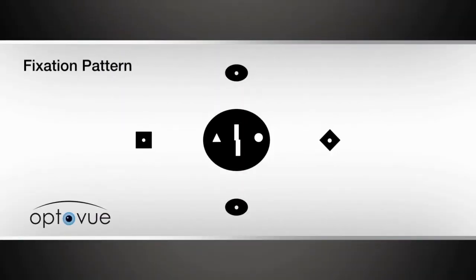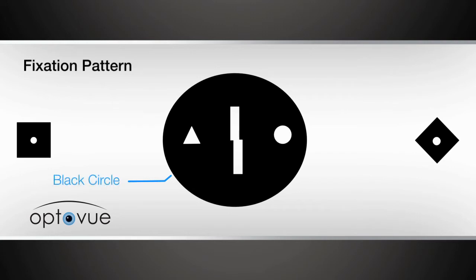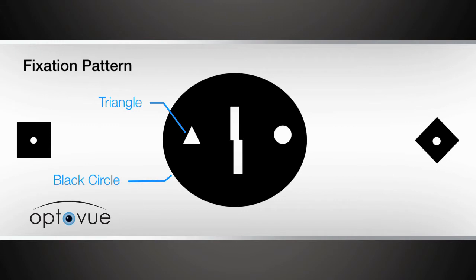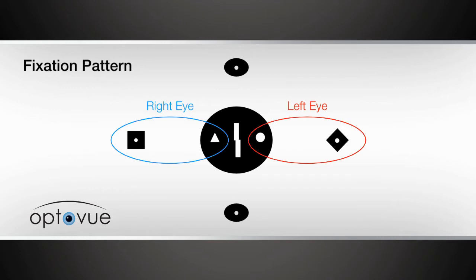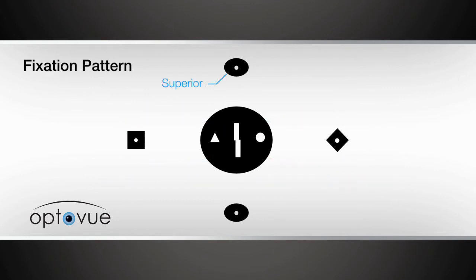Now let's look at the fixation pattern. The fixation pattern of the iCam has six objects. A large black circle in the center bisected by the focal bars contains a triangle for macular imaging of the right eye and a circle for macular imaging of the left eye. To obtain optic nerve images, use the square for the right eye and the diamond for the left. It may be beneficial to show the patient the fixation card and point out the shapes prior to imaging. There are two ovals — one for superior and the other for inferior. Any other locations of interest can be achieved by using the external fixation.